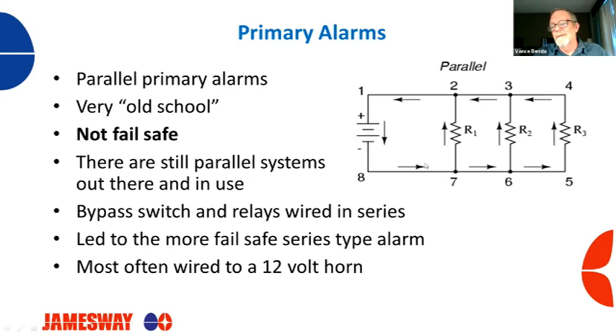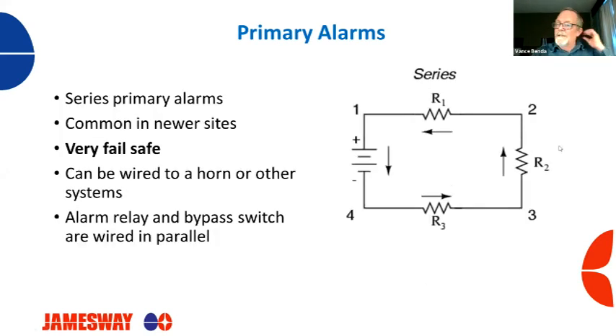And the way it works is almost completely opposite from series. This thing only sends a signal back to your control box when there's an alarm condition. The series alarm sends voltage continuously for no alarm and keeps a relay latched. Back in the day, when these systems were put in, almost all of them were simply connected to a 12-volt horn. Now, this picture, again, is not an actual alarm system, but it's a good little picture to help you understand what series wiring is.